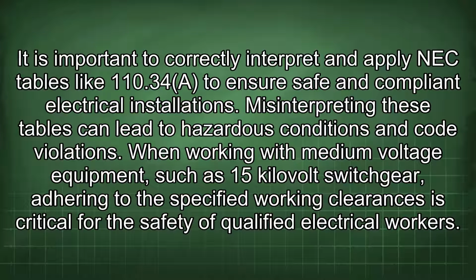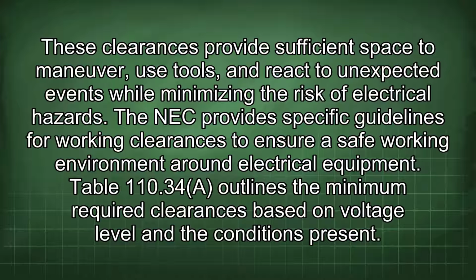It is important to correctly interpret and apply NEC tables like 110.34 to ensure safe and compliant electrical installations. Misinterpreting these tables can lead to hazardous conditions and code violations. When working with medium voltage equipment, such as 15 kV switchgear, adhering to the specified working clearances is critical for the safety of qualified electrical workers. These clearances provide sufficient space to maneuver, use tools, and react to unexpected events while minimizing the risk of electrical hazards.